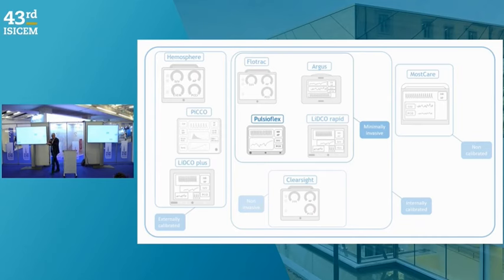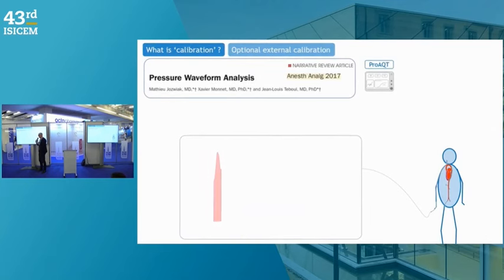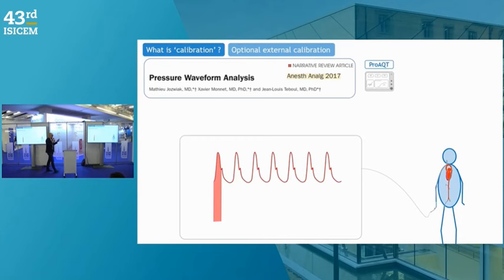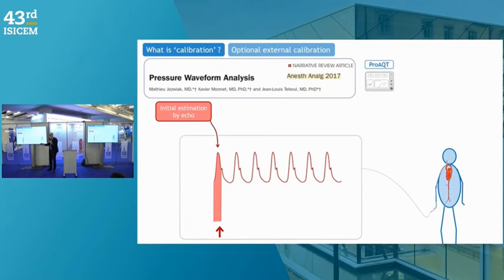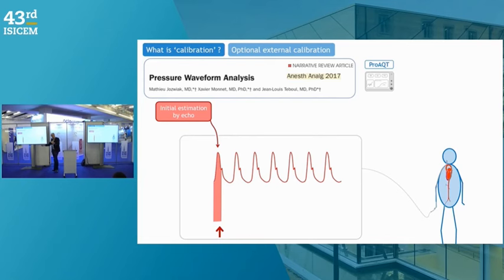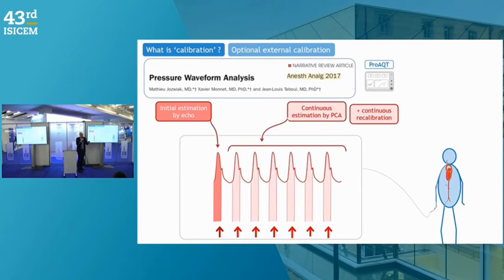One final word on the ProAQT PulsioFlex device: it is non-calibrated, but you can manually enter a cardiac output value estimated by echocardiography — measuring VTI and the LV outflow tract area. You enter this value, and the system becomes calibrated. It is not simple, since you must measure cardiac output with echo and then enter it into the device, but it gives a continuously displayed calibrated cardiac output.